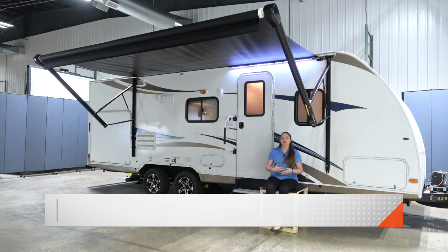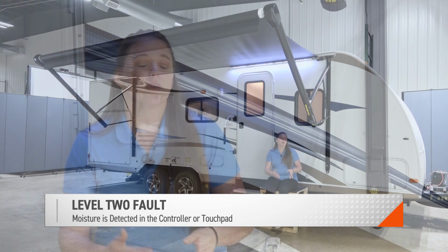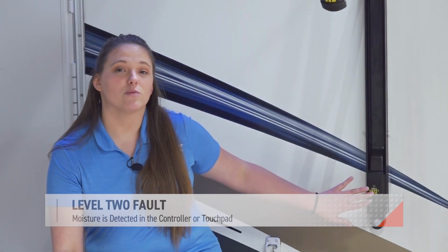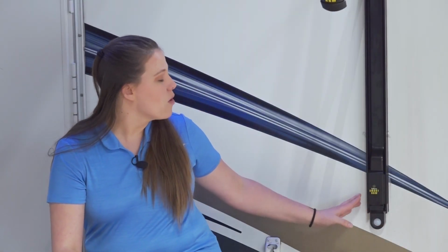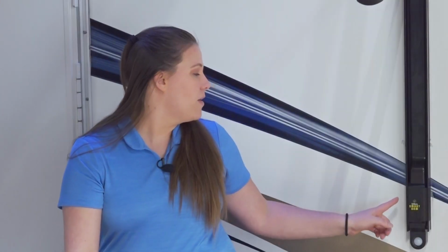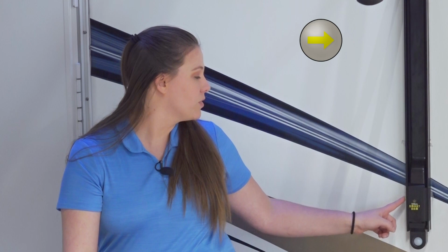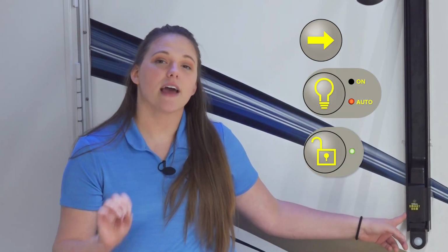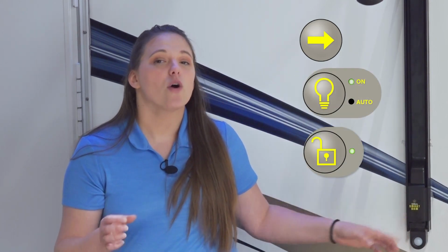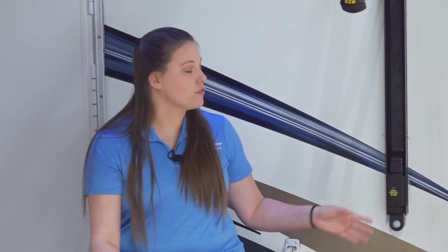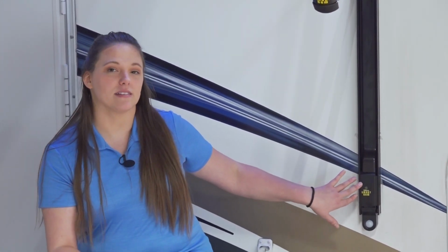You can also experience what's called a level 2 fault, and this is when your controller senses moisture either in the controller or at the touchpad. The symptoms for this fault are that your extend switch, your light switch, and that green LED at the lock will also blink. The reason that your controller is preventing you from operating at the touchpad is because it's trying to prevent damage while the moisture is inside the system.